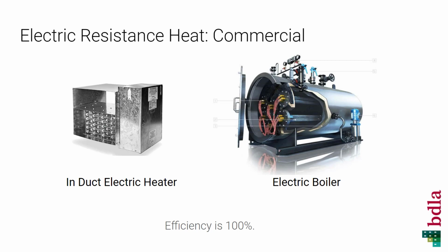Electric resistance can also be applied in a commercial setting, either as an electric resistance heater installed directly in a duct, or as an electric boiler. An electric boiler would heat hot water, which is then distributed around the building. Electric resistance is 100% efficient, so all of the electricity is transferred into heat.